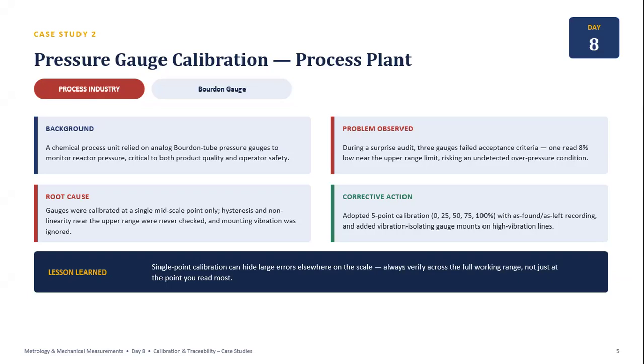The corrective action was to introduce 5-point calibration at 0, 25, 50, 75 and 100 percent of the range, together with as-found and as-left records. The important lesson is that single-point calibration can hide significant errors elsewhere in the measurement range. Calibration should represent the actual operating range of the instrument.